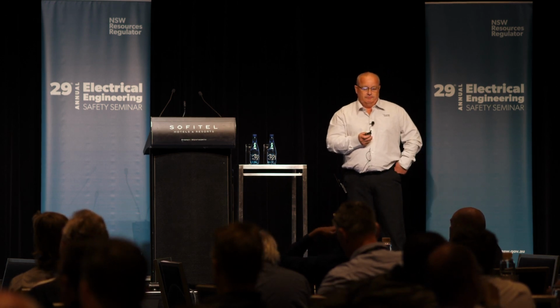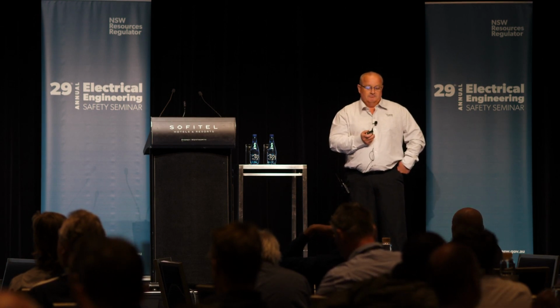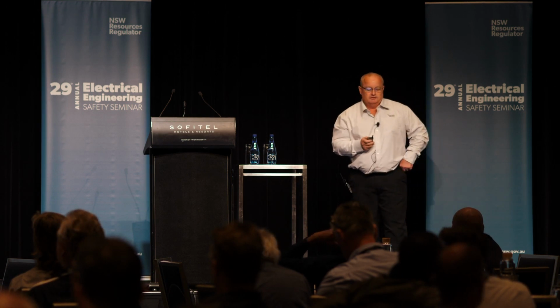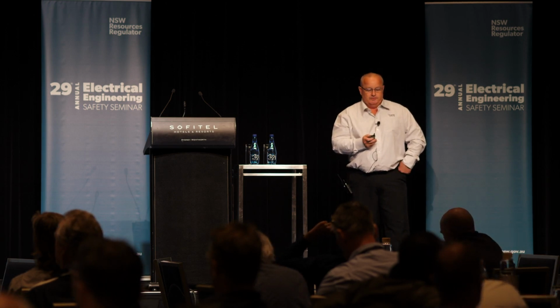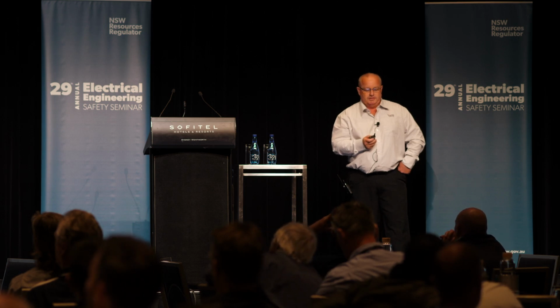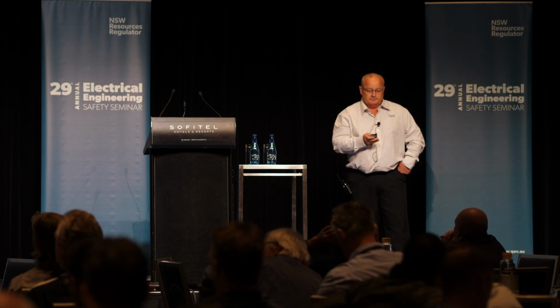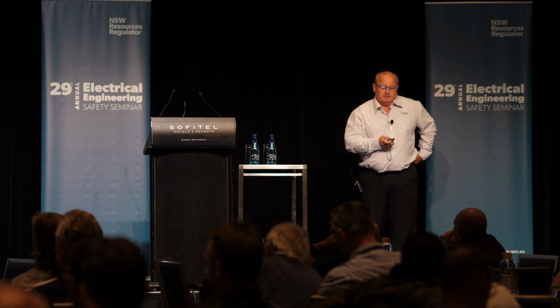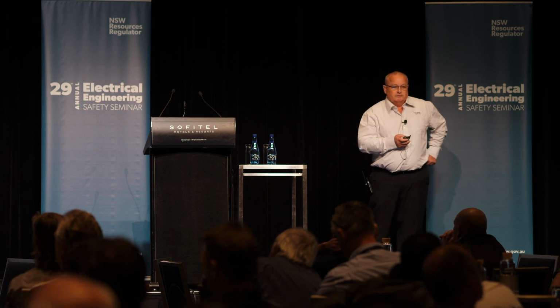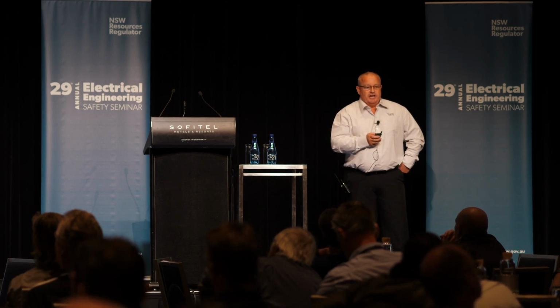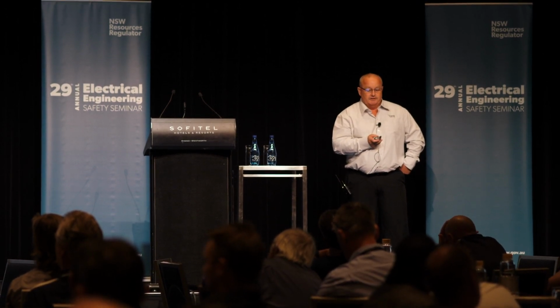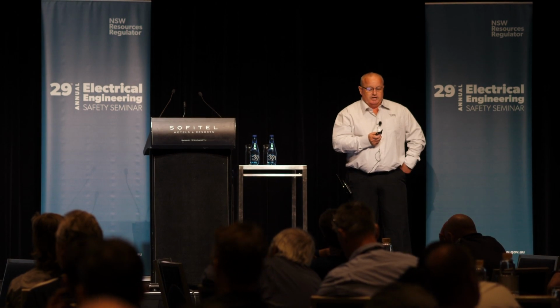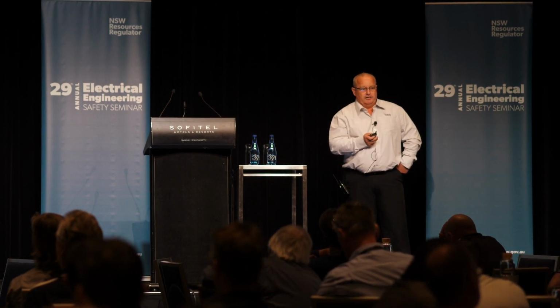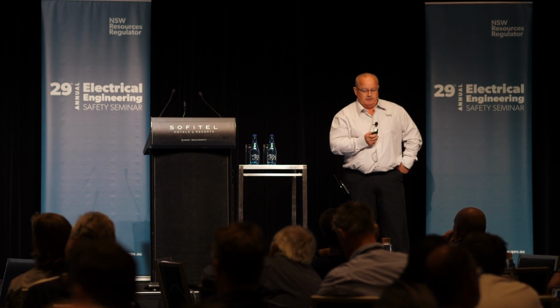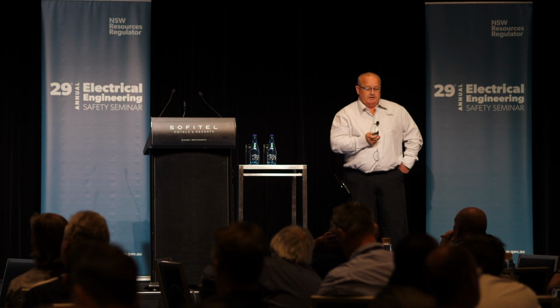So your standard ground fault, whether you're using a summation in a circuit breaker or earth leakage, RCD, CT on MEN link, they're not going to work. Sorry. Transfer voltage will still need to be controlled under your current protection schemes because based on the type of system that goes in, it may reduce it, but it's unlikely. Equipment selections will still be based on IT systems. Isolation transformers, we looked at them as far as isolating their network from ours, so put an isolation transformer in. But the problem with that is you can't get far enough away from their system to get a remote earth to get the earth transfers because in this case this is a residential area. Basically on mine sites you may be able to do something.